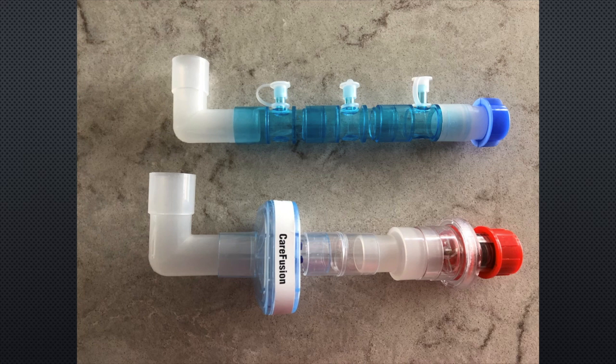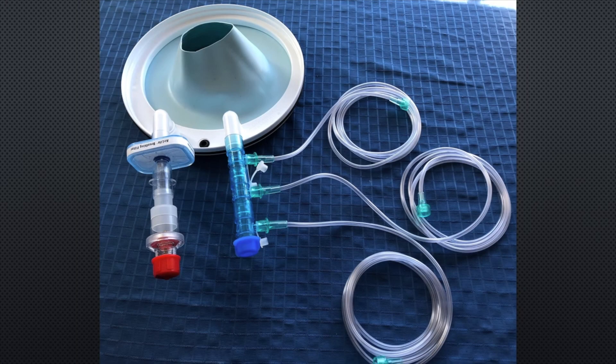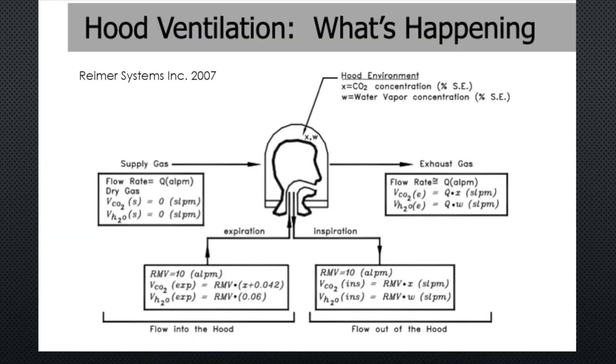This is the alternative setup of the supply side assembly set up for CPAP. High flow rates are recommended to ensure carbon dioxide is not rebreathed.